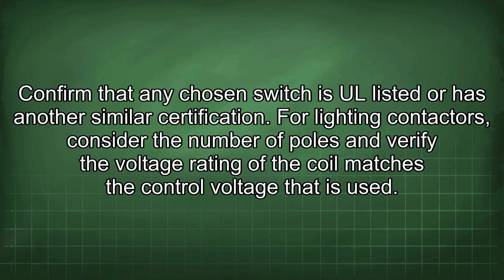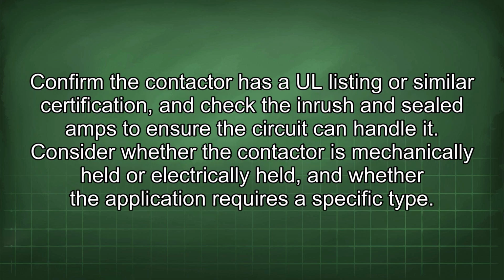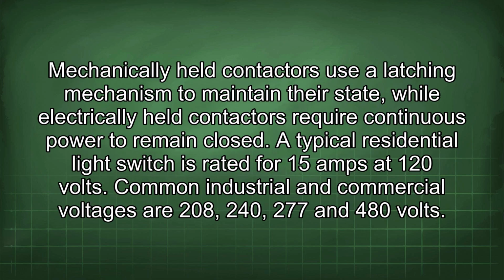For lighting contactors, consider the number of poles and verify the voltage rating, and that the coil matches the control voltage that is used. Confirm the contactor has a UL listing or similar certification, and check the inrush and sealed amps to ensure the circuit can handle it. Consider whether the contactor is mechanically held or electrically held, and whether the application requires a specific type. Mechanically held contactors use a latching mechanism to maintain their state, while electrically held contactors require continuous power to remain closed. A typical residential light switch is rated for 15 amps at 120 volts.